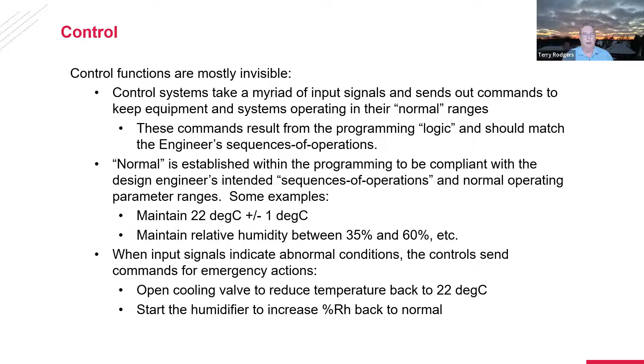The key to stable and effective control is to have a comprehensive startup and testing and commissioning of the infrastructure, but also the controls that manage them. Systems and equipment testing, especially for your complex facilities, should be done at various load profiles if the building is going to experience various load profiles. So commercial office buildings, that's usually not the case. They're pretty stable. You load up the building with occupancy and it's pretty consistent over time.